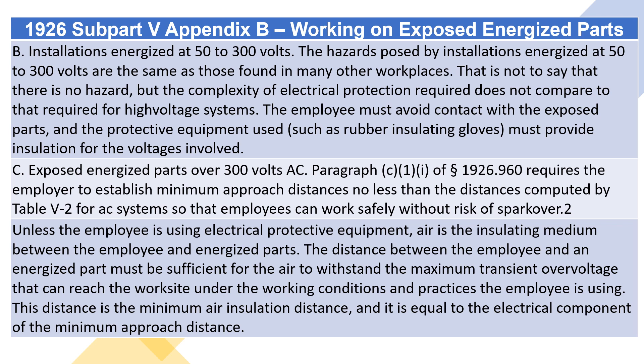The hazards posed by installations energized at 50 to 300 volts are the same as those found in many other workplaces. That is not to say that there is no hazard, but the complexity of electrical protection required does not compare to that required for high voltage systems. The employee must avoid contact with the exposed parts, and the protective equipment used, such as rubber insulating gloves, must provide insulation for the voltages involved. Paragraph C.1.I of Section 1926.960 requires the employer to establish minimum approach distances no less than the distances computed by Table V-2 for AC systems so that employees can work safely without risk of spark over.